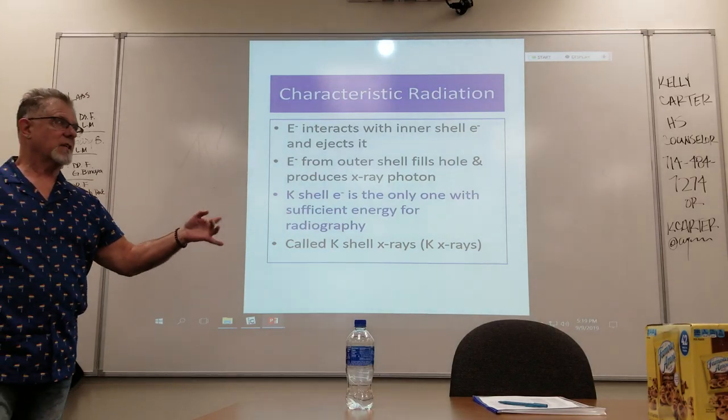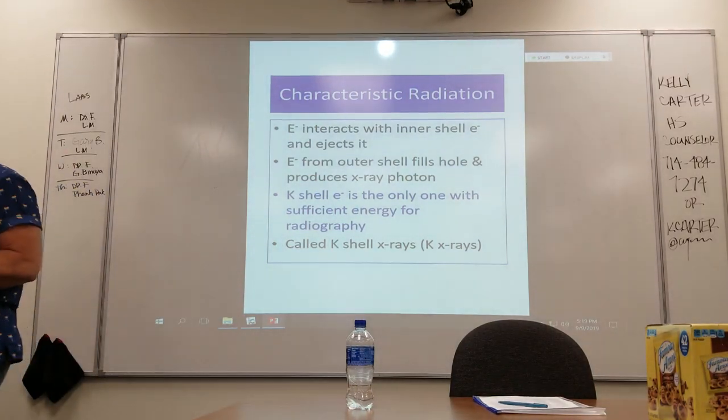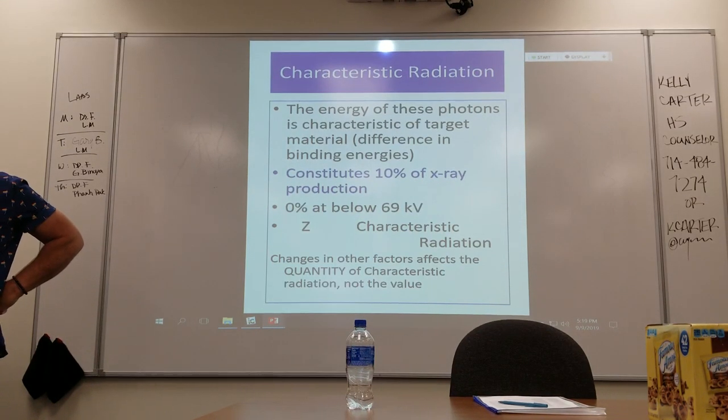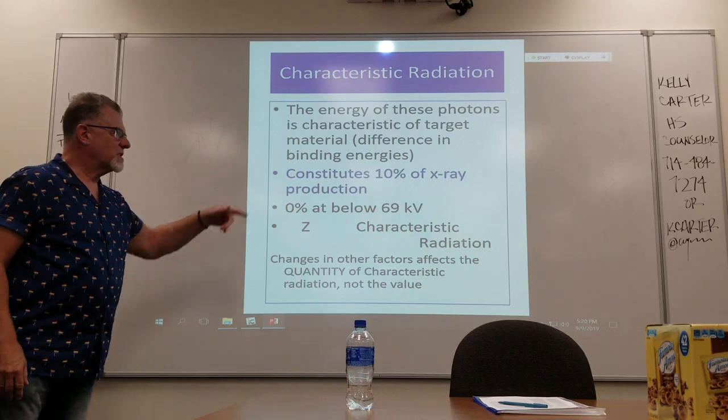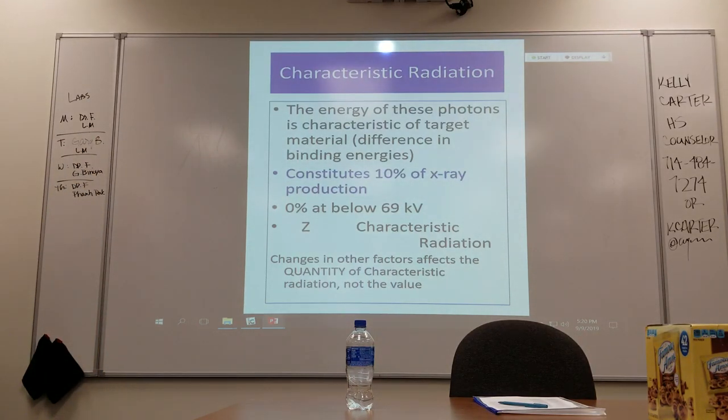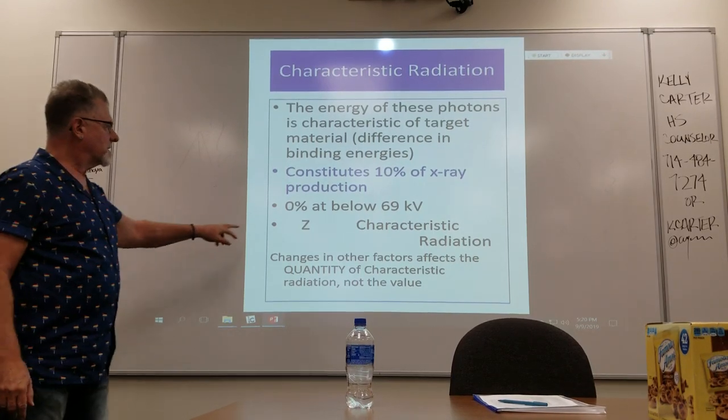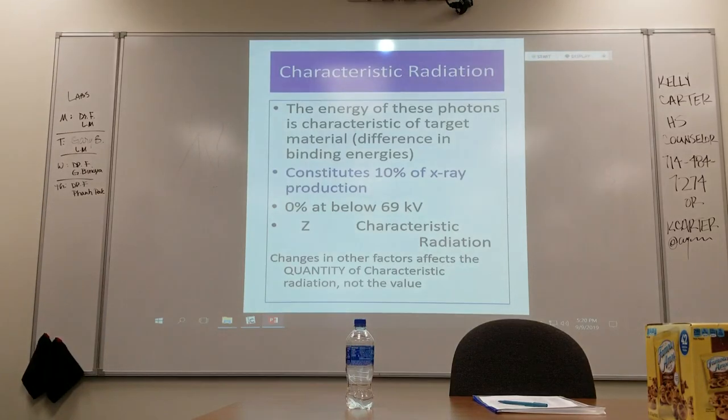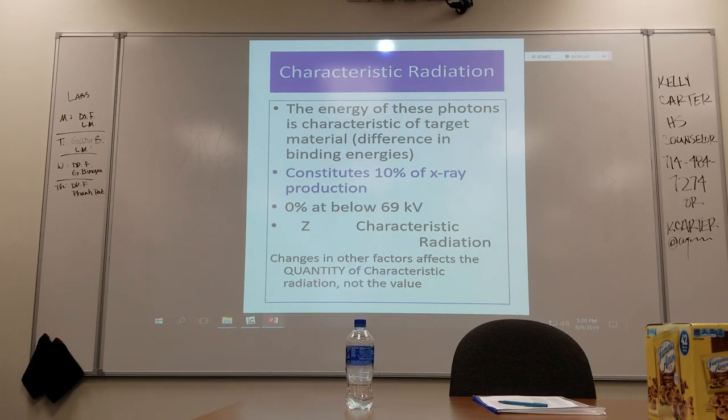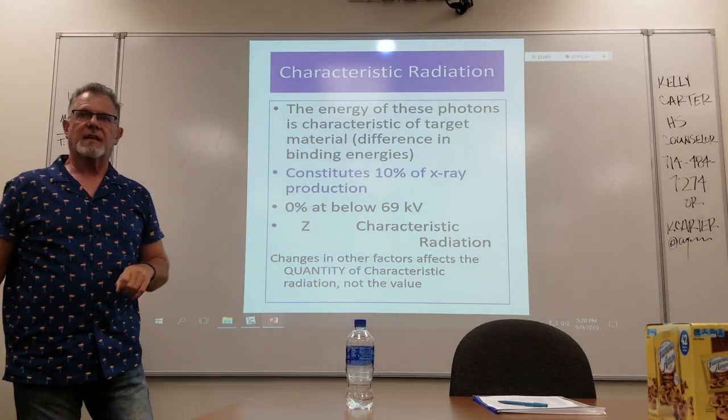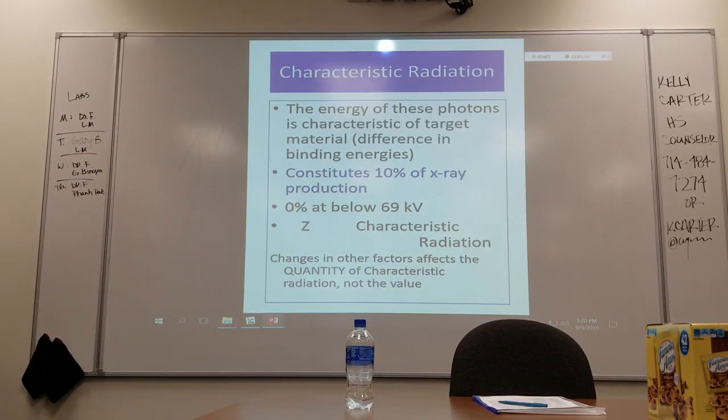The energy is characteristic of the target material. It's due to the difference in binding energy. Radiation is about 10% of the X-ray production for the X-ray tubes that we use that are tungsten base. You will not get any characteristic below 69 kV because that's the binding energy, the highest binding energy of the K shell for tungsten. At 68 you're not going to get anything, you have to be 69 or above. Changes in other factors will affect the quantity of characteristic radiation but not the value. This is a fingerprint, it's an identification.